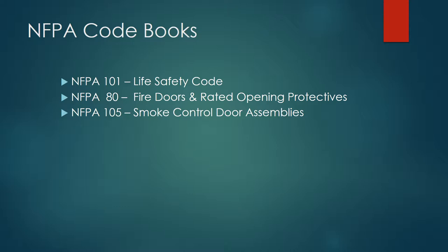The NFPA code books we'll primarily touch on are NFPA 101 Life Safety Code — specifically chapter 8 on doors and openings, and chapters 18 and 19 — and NFPA 80, fire doors and rated openings, which is the heart of understanding the maintenance and requirements of door operation. NFPA 105 covers smoke control door assemblies, which gets into HVAC, heating and cooling, and how air control as it relates to smoke affects doors.